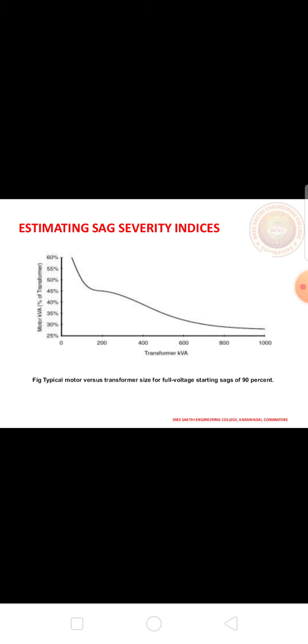First, the various causes of voltage sag in a power system. It can be caused by faults, more than 70%, or weather related events such as lightning on the distribution or transmission systems, or by switching on loads with large initial starting and inrush current such as motors, transformers and large DC power supplies. It is associated with a system fault but can also be caused by the switching of heavy loads or starting of large motors. This is voltage sag and its causes.